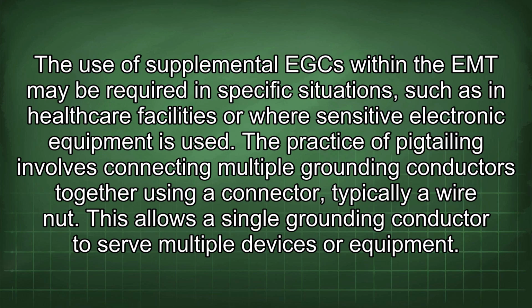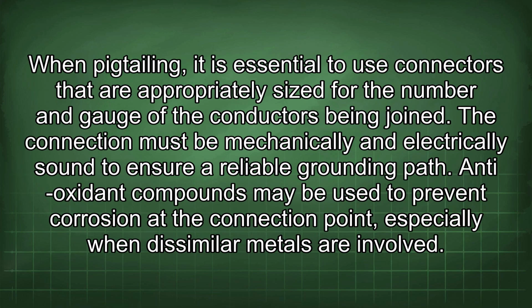The practice of pigtailing involves connecting multiple grounding conductors together using a connector, typically a wire nut. This allows the single grounding conductor to serve multiple devices or equipment. When pigtailing, it is essential to use connectors that are appropriately sized for the number and gauge of the conductors being joined. The connection must be mechanically and electrically sound to ensure a reliable grounding path. Antioxidant compounds may be used to prevent corrosion at the connection point, especially when dissimilar metals are involved.